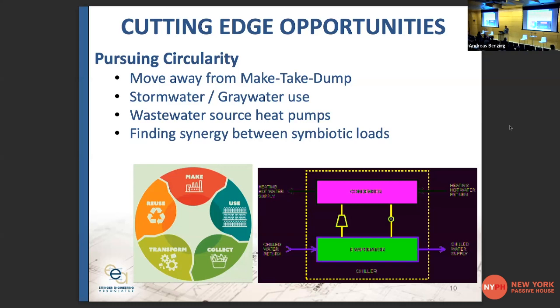Let's talk about how we can find synergy between symbiotic loads, as a kind of near closing point in the same space. Let's refresh for a second on what a heat pump is. If I'm a gas boiler making energy by combustion, I'm burning something, making a chemical change to release heat. Heat pumps move heat—that's all they do. When we cool this room, we're taking heat and sending it outside.